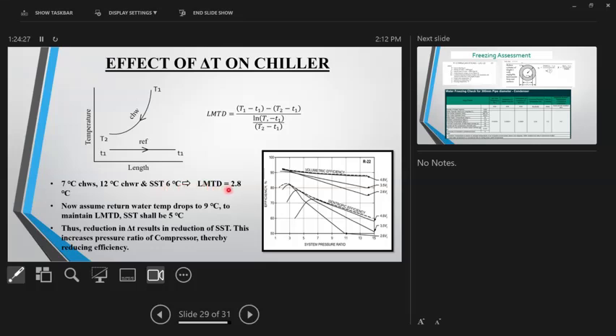So the manufacturer has selected the heat exchanger for an LMTD of 2.8. LMTD is nothing but, if you put the temperatures, this 7, 12 and so on, into this equation, the log mean temperature difference for this condition for that evaporator is 2.8.